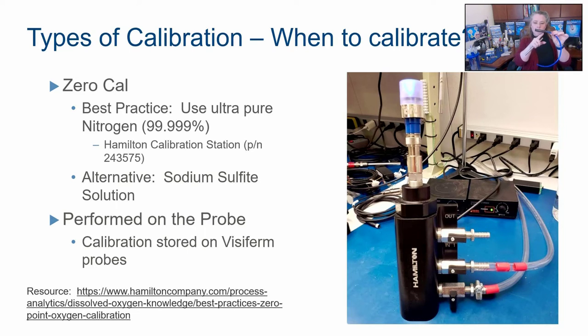So you want to bring the gas into something where there's space between where the gas starts flowing at the 2 to 3 PSI and where the probe reaches it. This happens to be a tube that allows this much space. That space means the gas has time to come up to room temperature and equilibrate. I would literally put this probe like this and let it hang out in flowing gas for about 3 to 5 minutes. And then I would do a zero cal using, I'm not going to show you how to do this in here, the Hamilton software. If you're doing other probes, they have different software to do a zero cal. And I say, this is zero cal, and my calibration says, yes, it is. Good to know. You will fail a calibration if the temperature fluctuation on your probe is too much. It has to be very narrow, within 0.02 degrees Celsius change over that time. But now you're blanketing with it and that's your zero cal.